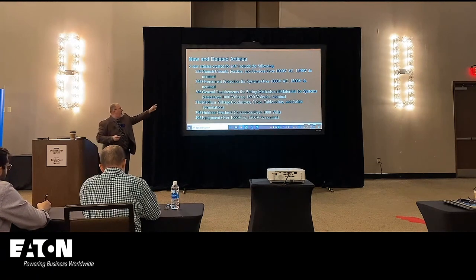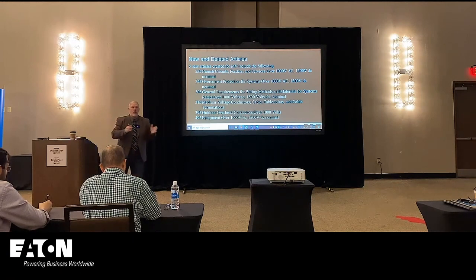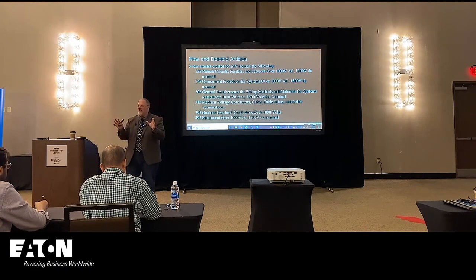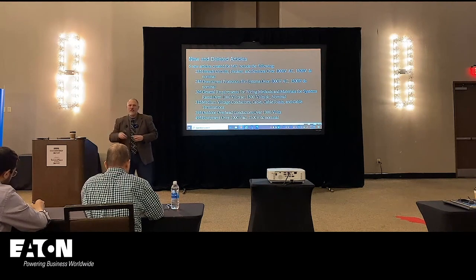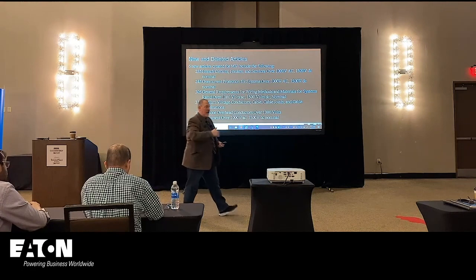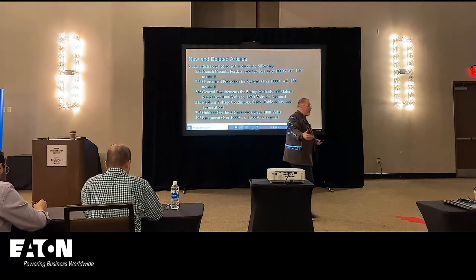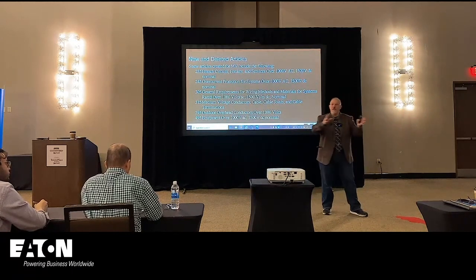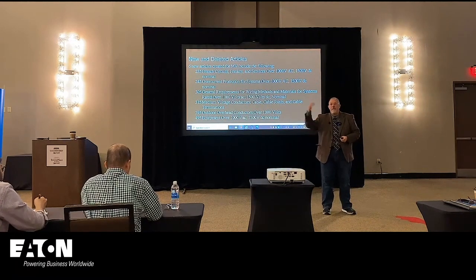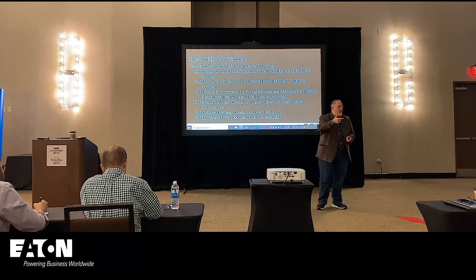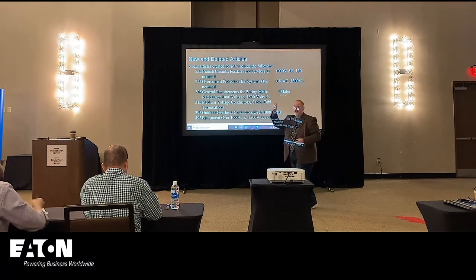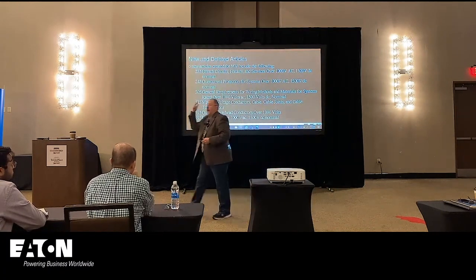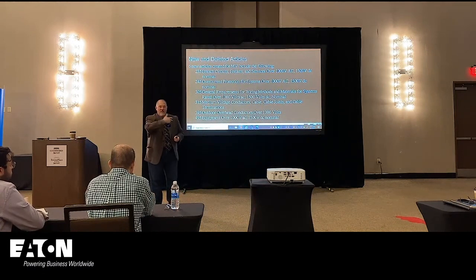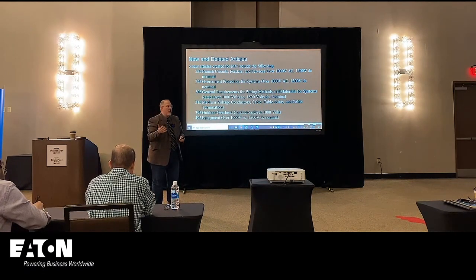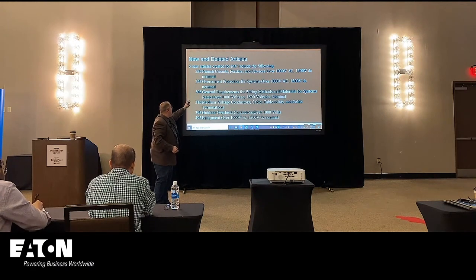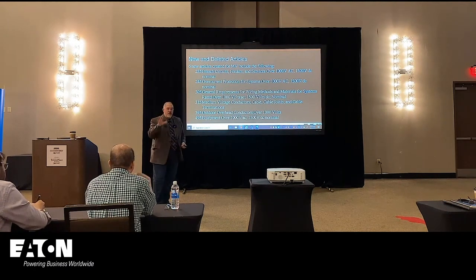These new articles, 235, began in panel 2. In 210, we had like 2 sections that were addressing medium voltage applications. But in reality, everything in 210 for branch circuits applies to medium voltage applications. So we moved a lot of the 210 requirements into 235. And then panel 10 did the same thing for 230 for services, 225 for outdoor feeders and outdoor branch circuits. So you've got 210, 215 for feeders in there. You have 225 and 230 all in Article 235. Branch circuits, feeders, services over 1,000 volts. So that's your medium voltage home.